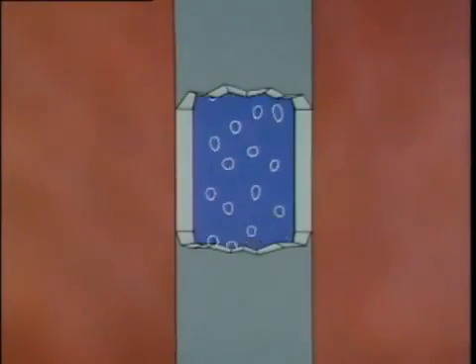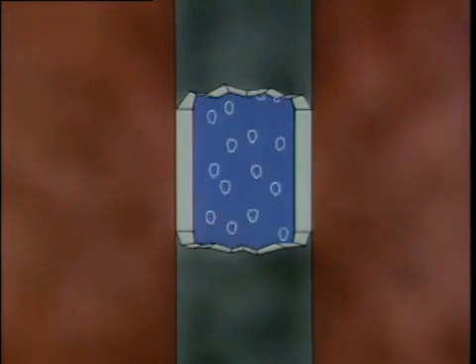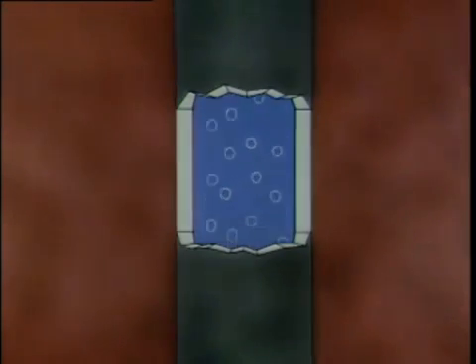In boilers that burn coal or oil, another problem that can affect heat transfer is the buildup of soot. Soot is created by ash and unburned fuel particles in the combustion gases. Soot buildup insulates the surfaces, preventing good heat transfer. When this occurs, the amount of heat transferred to the water decreases. As a result, heat is wasted — it escapes with the gases routed out of the boiler, reducing boiler efficiency.